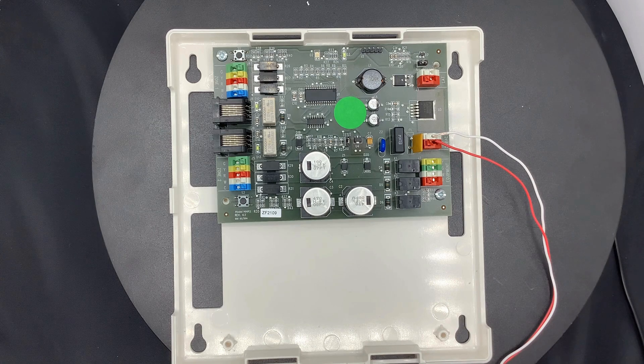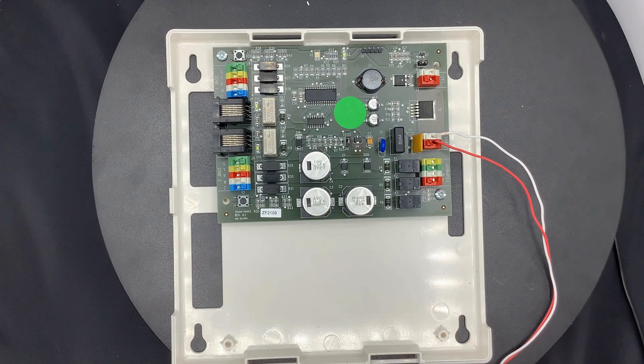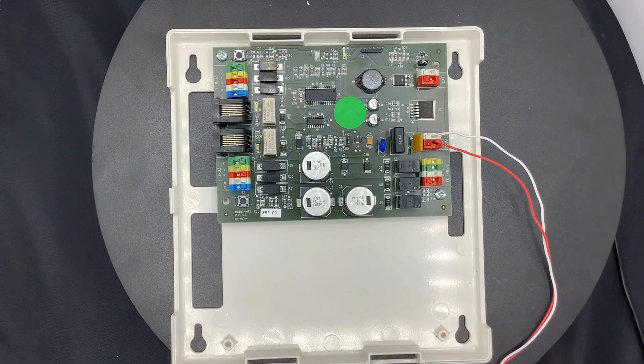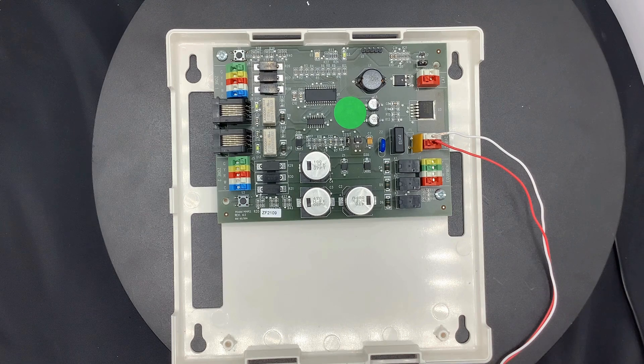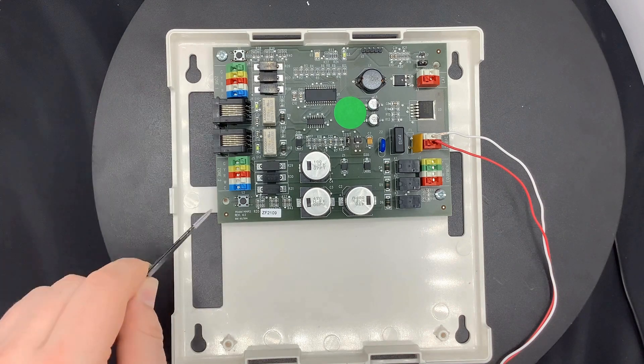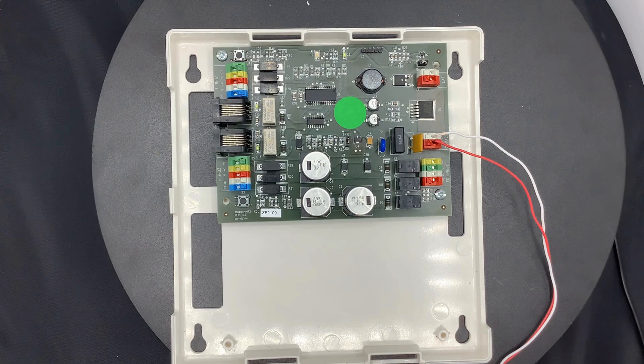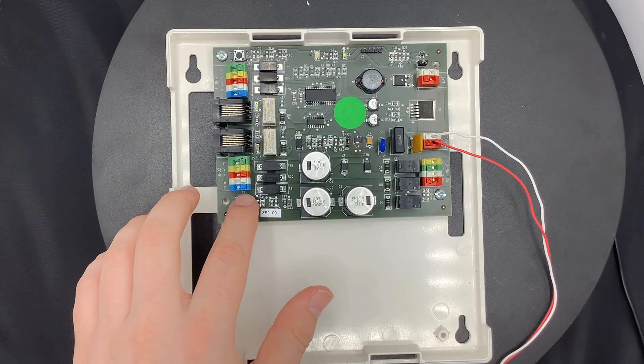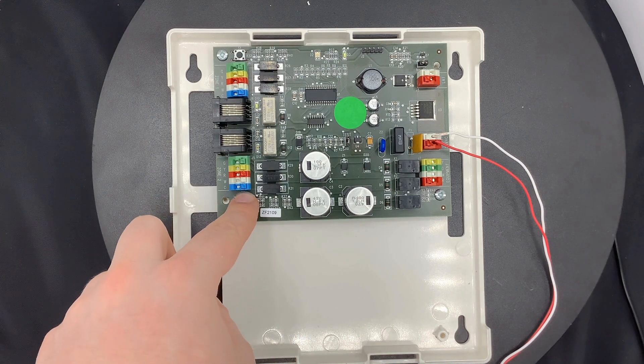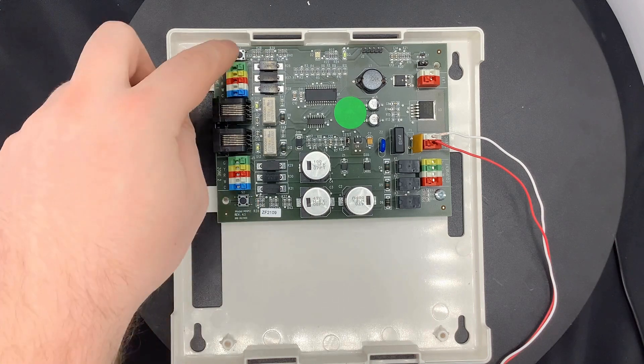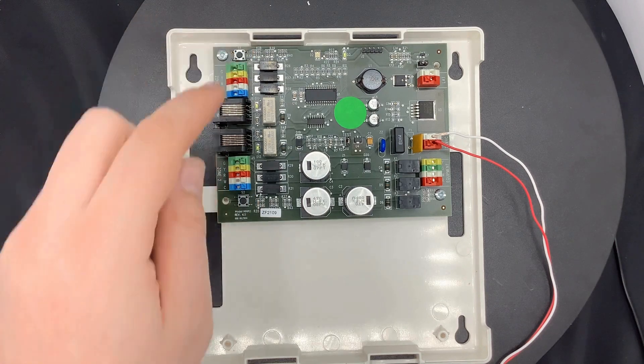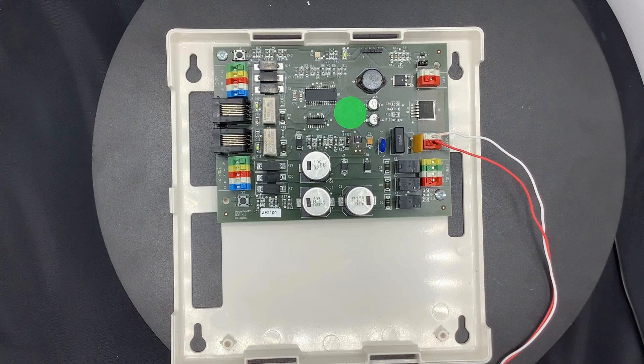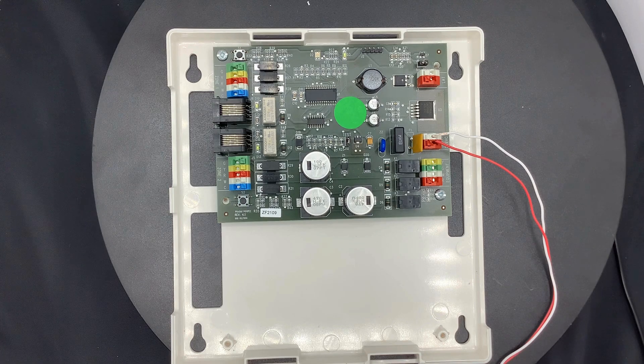The last step in troubleshooting an MMP2 board is to use your actuator motor buttons. These buttons can be found on the top left and the bottom left of the board. When you click this button, it will activate the motor of that damper. This is used for troubleshooting if the motor and damper are working, versus if there is a problem with the board itself.